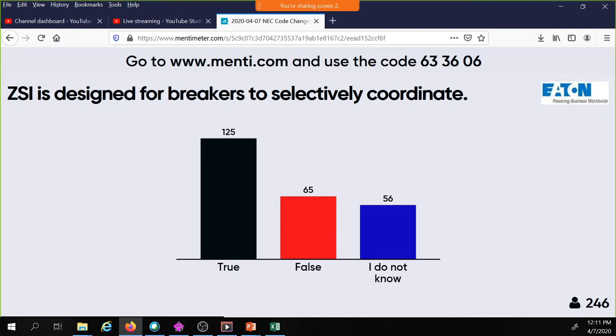Zone selective interlocking does not get you selective coordination. ZSI is an arc reduction equipment protection technology. And we're going to talk about this to help you completely understand that, so that the next time you get this question, I'm going to have all 260 of you in that false bucket, and I'm going to feel great about myself. But zone selective interlocking, that's why it's a part of 240.87 as an arc reduction technology.